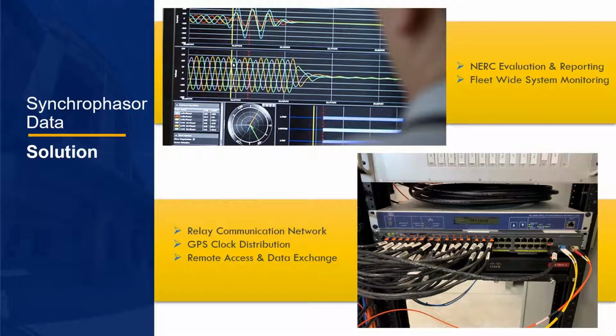One of the requested features for this project was to add the ability to record the generator's synchrophasors via the relay PMU functionality. Capturing and visualizing this data supports NERC-required response evaluation reporting, which historically is done during generation downtime, requiring unit operation in non-normal conditions. In addition, rolling out PMU capturing fleet-wide can support a system monitoring program and provide a microgrid operation to improve grid reliability, system response methods, and future planning.